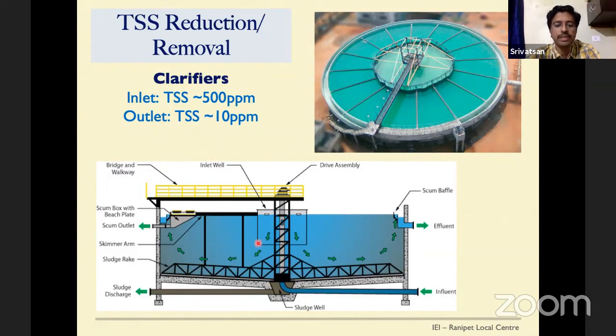Whatever suspended solids is there, if you allow time, it will settle automatically at the bottom, and we scrape it, collect the sludge and dispose of it. Whatever water comes up the clarifier gets collected in the launders or weir arrangement, and it will be of lesser suspended solids content. Basically, we have a TSS level of up to 500 ppm at the inlet of clarifiers, and what we get at the outlet of the clarifier is around 10 ppm.